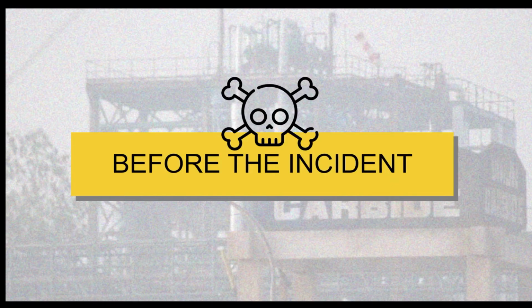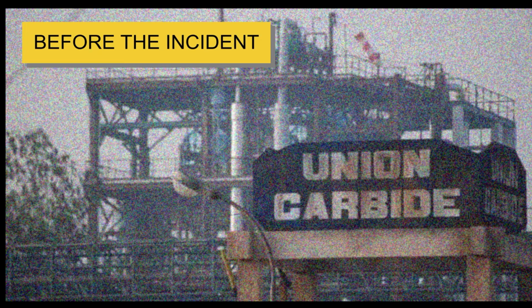And the last one is that instruments at the plant were unreliable. According to Shakil Qureshi, the methyl isocyanate supervisor on duty at the time of the accident, he ignored the initial warning of the accident, a gauge indication that pressure in one of three methyl isocyanate storage tanks had risen fivefold in an hour. With that, they neglected safety standards set in Chapter 27 of the PME Code 2008, which is all about instrumentation. So this is the image before the incident.